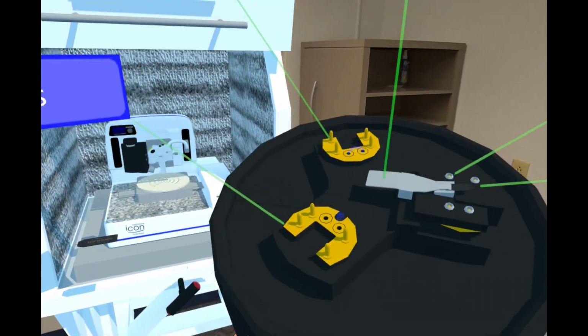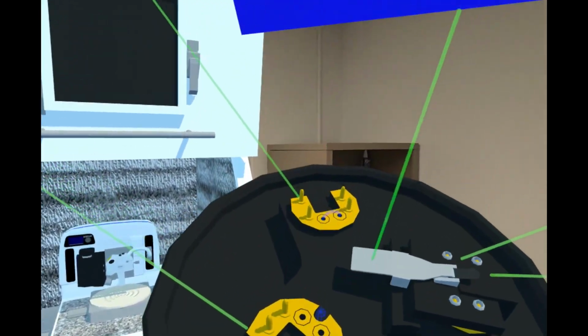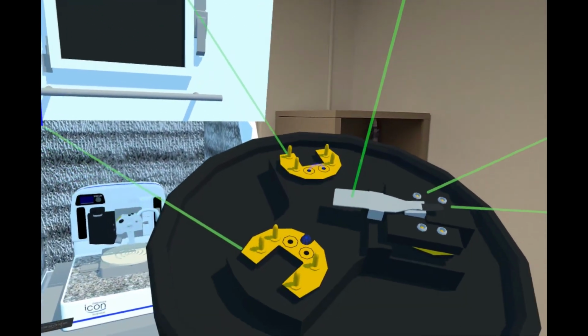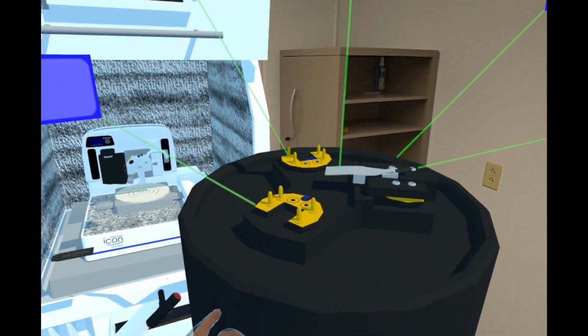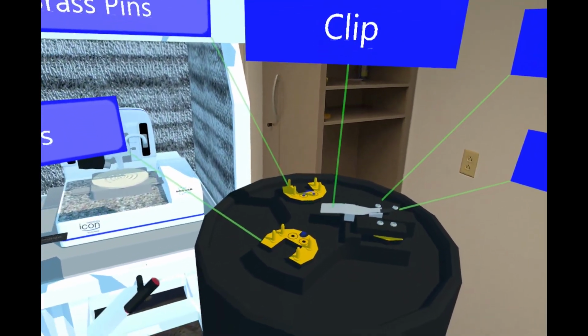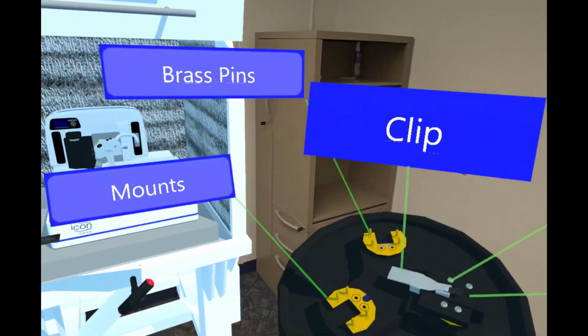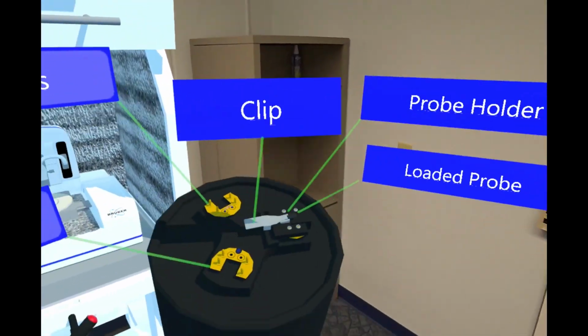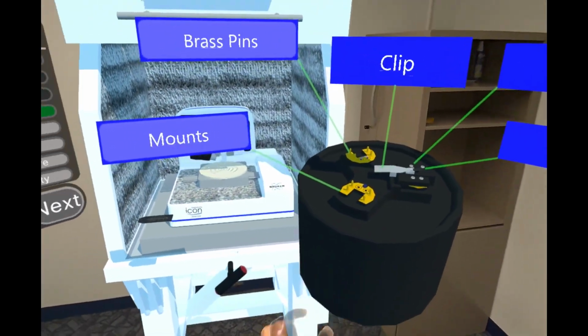Working in fluid requires a completely different mounting method, which is a very different probe holder design. The third position is for the electrical probe holder and has none of the extra flat platform material and nothing special about it. It's wide open because of the shape of the electrical probe holder. Otherwise, it has the same mounting mechanism as the standard probe holder.